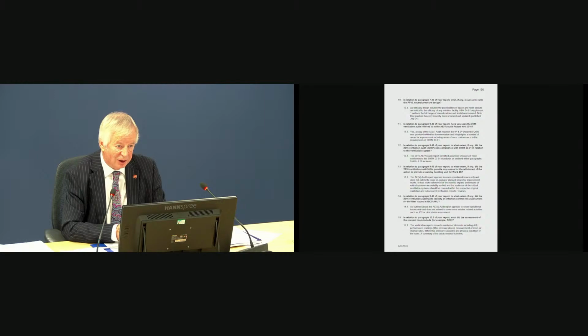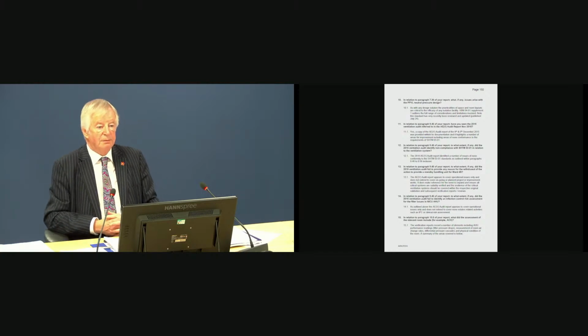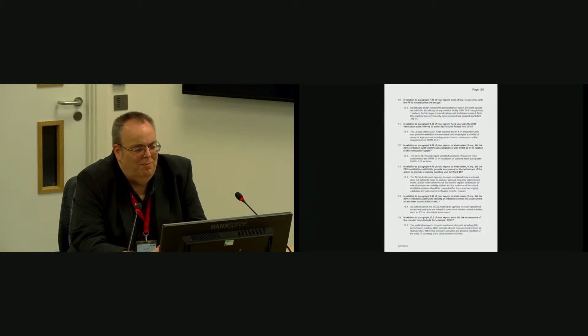Are there particular issues that arise with that compared to, say, a negative pressure room or positive pressure room? At the time that this was written, the HBN 0401, a PPVL incorporates a lobby entrance. At the time, HBN 0401 did not specify lobbies on positive or negative pressure isolation rooms. That has since been updated, and the latest HBN guidance now specifies that lobbies should be provided for all isolation rooms, be positive, negative, or neutral pressure.